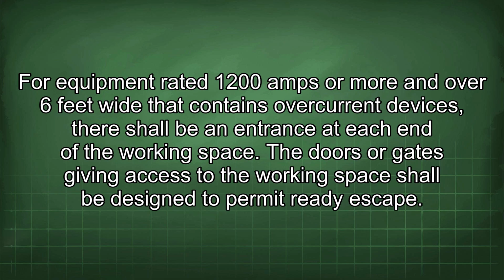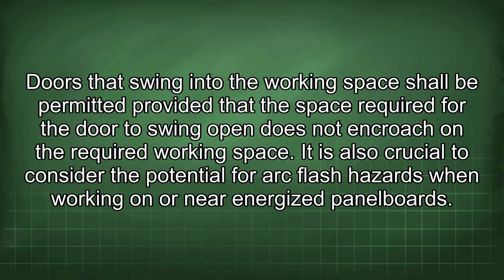The doors or gates giving access to the working space shall be designed to permit ready escape. Doors that swing into the working space shall be permitted provided that the space required for the door to swing open does not encroach on the required working space.